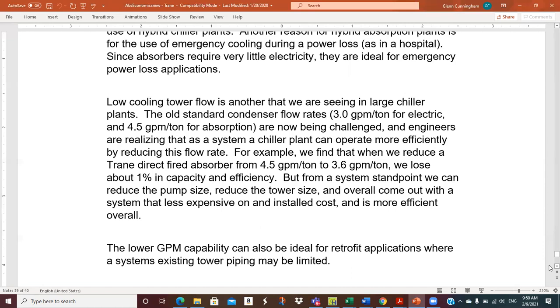So we typically come in at 85 and go out at 103, whereas on the centrifugal, we would come in at 85 and go out at 95. Those are kind of standard numbers, and some of those numbers are being challenged too, to increase the range so that you can decrease flow rates. But at any rate, the old number on the absorber was 4.5 GPM per ton. And you need to know that. That's part of what you're in this class to learn.